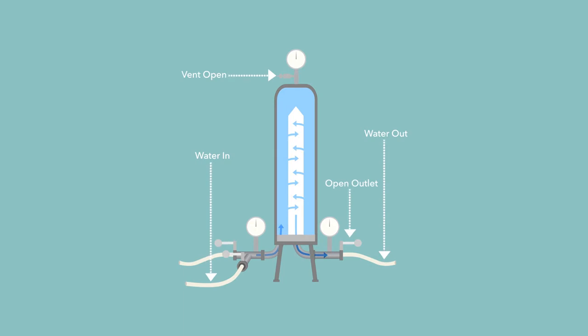At this point, the filter can also be sanitized, either by increasing water temperature to 180 degrees Fahrenheit for the prescribed period of time, or by draining the housing and applying steam. All caution and best practices should be followed when handling high temperature water or steam.